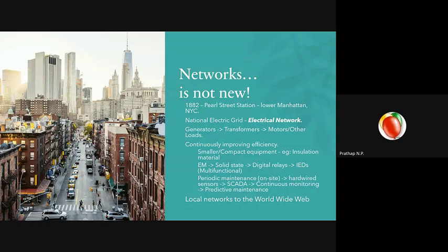And it's a very delicate equipment, so you have to tune it very precisely in order to make it work correctly. But then, as we had solid states come in, all those sizes started to come down. And then we started having digital relays, and it got even more compact, and it started to combine protective elements together. Like you would have overcurrent, under voltage, over frequency, under frequency, over voltage, under voltage, everything in a single box. Instead of separate relays taking up an entire control panel, you will have probably one or two relays to do the entire job.